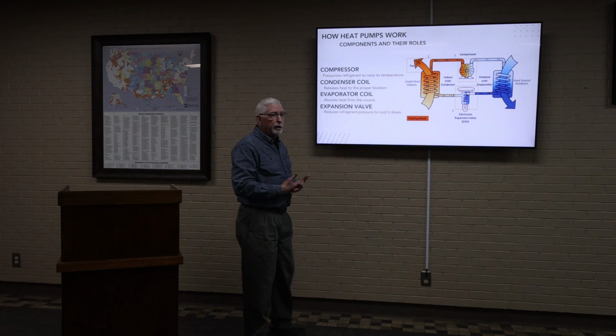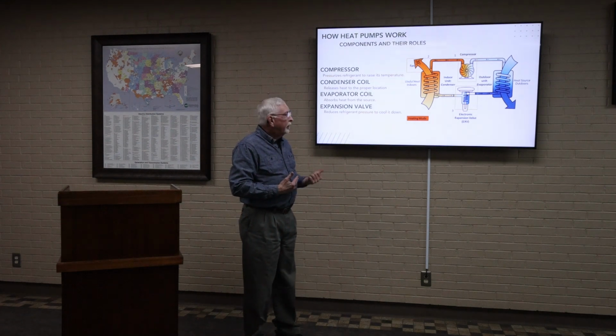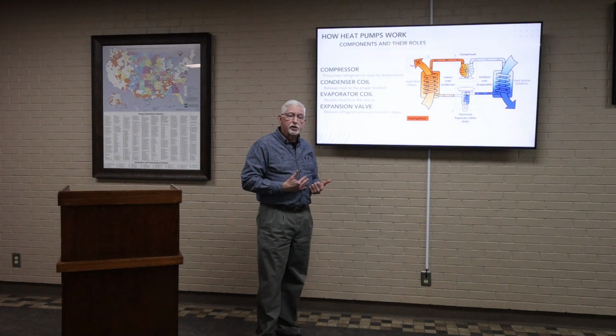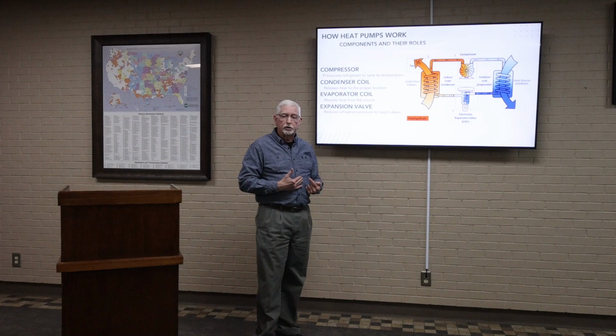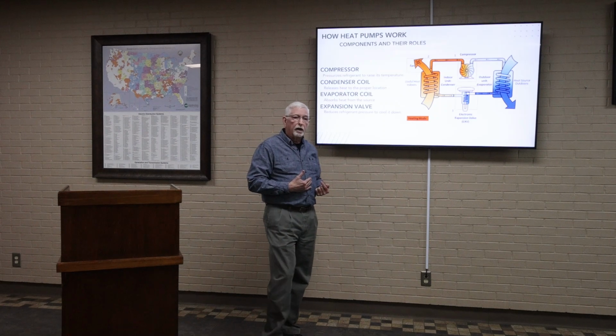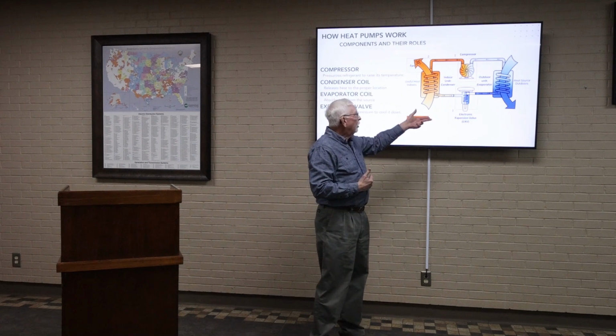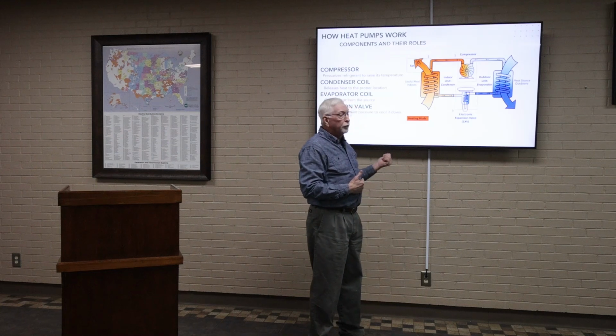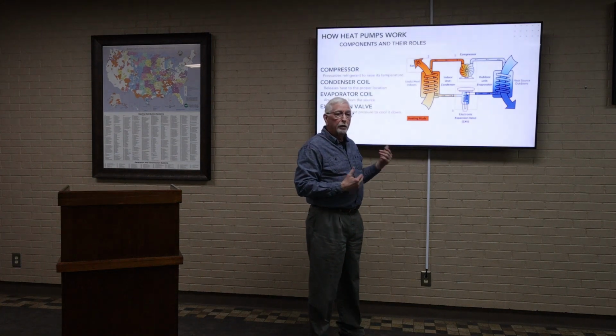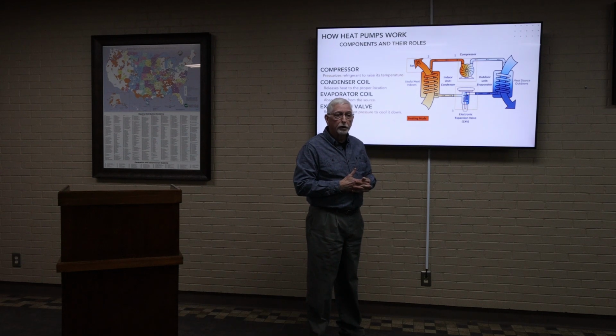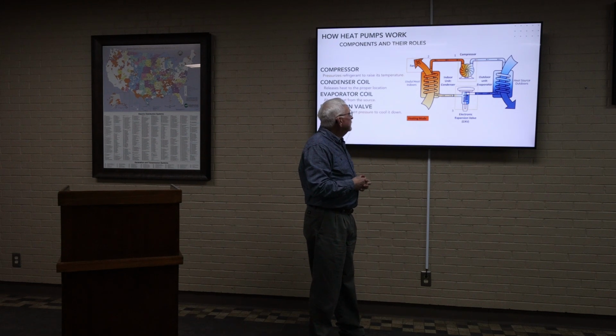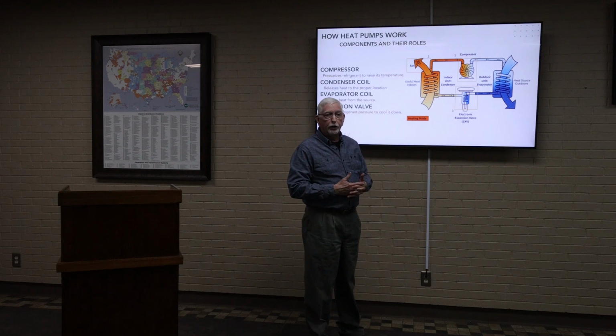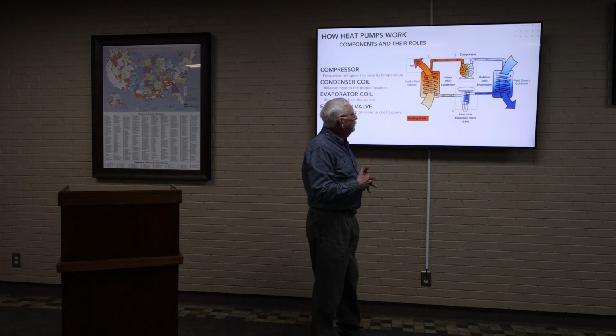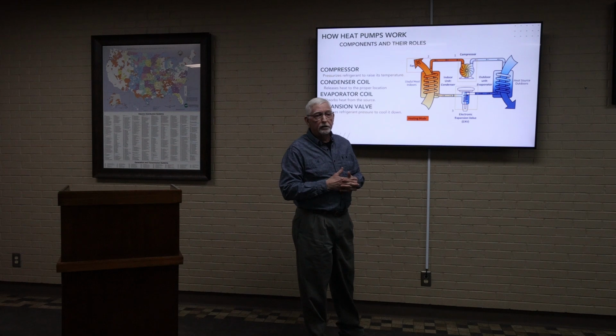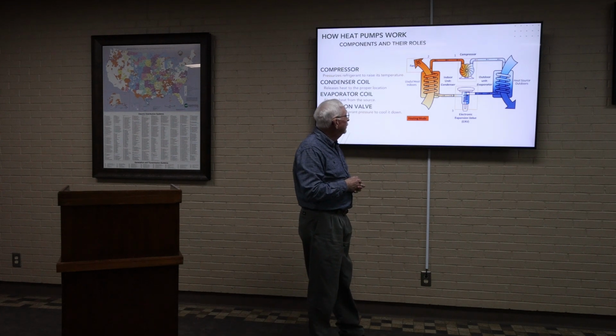So to get the best performance out of your heat pump system, the ideal thing is to have it cleaned and checked at least once a year by a good, qualified contractor. Have them do a coil clean, indoor and outdoor, check the refrigerant level to make sure it's up to par, and make sure all your electrical connections are good. That should be good for a year, but I personally like to do this in the springtime before cooling season, and also in August or September before the heating season kicks in.